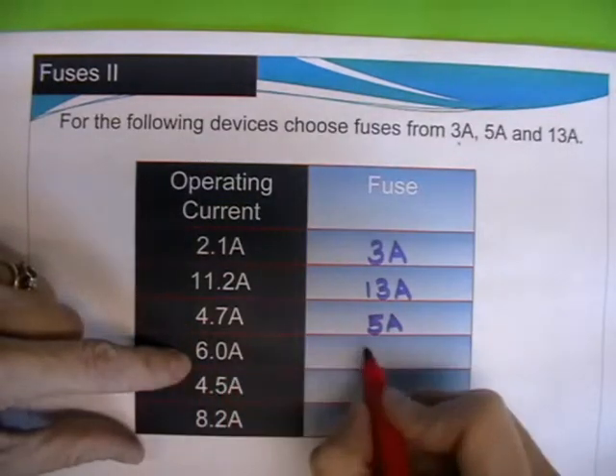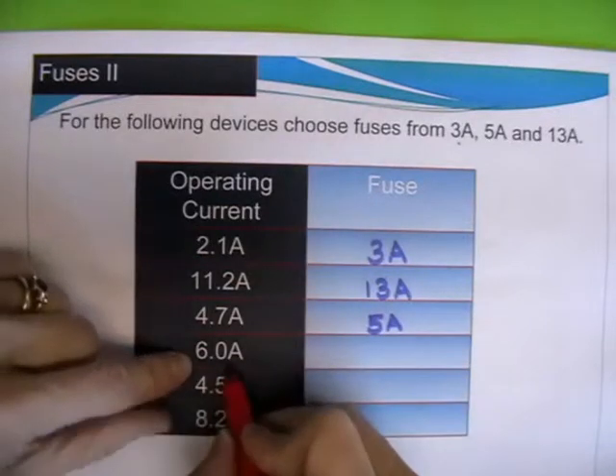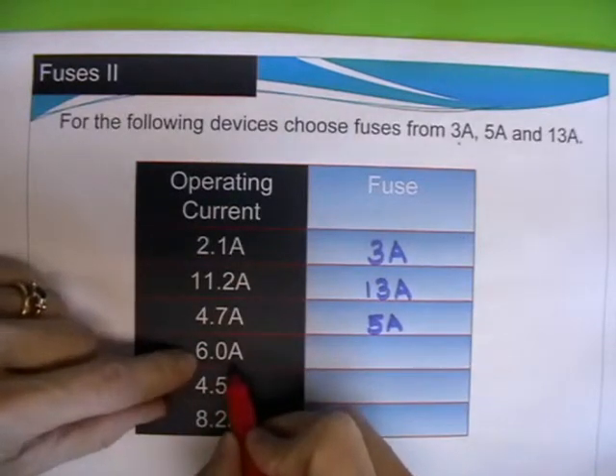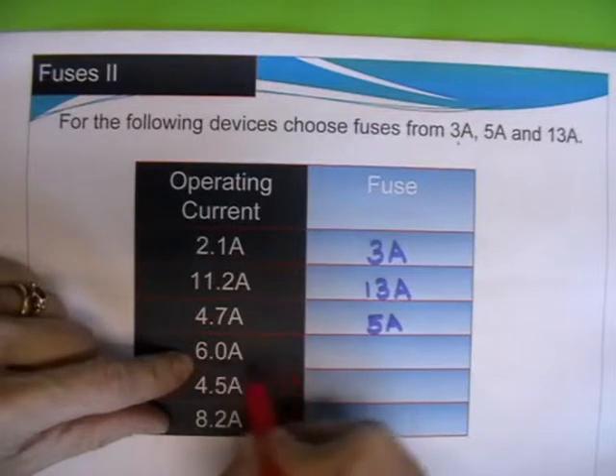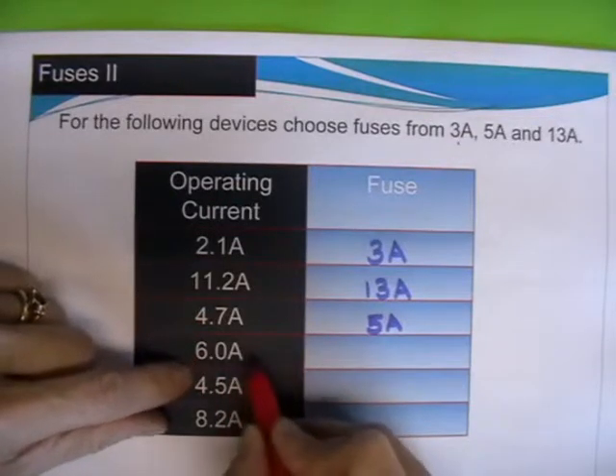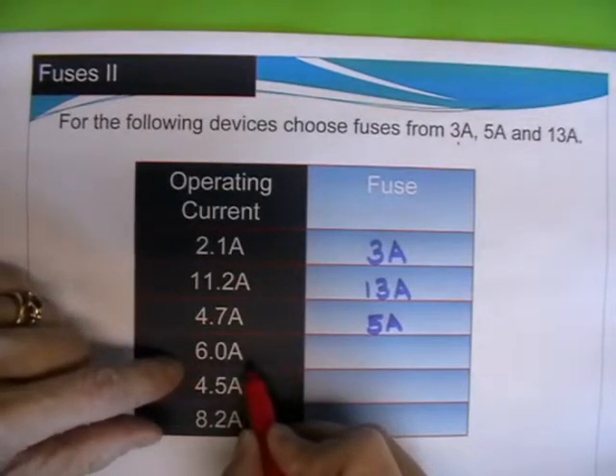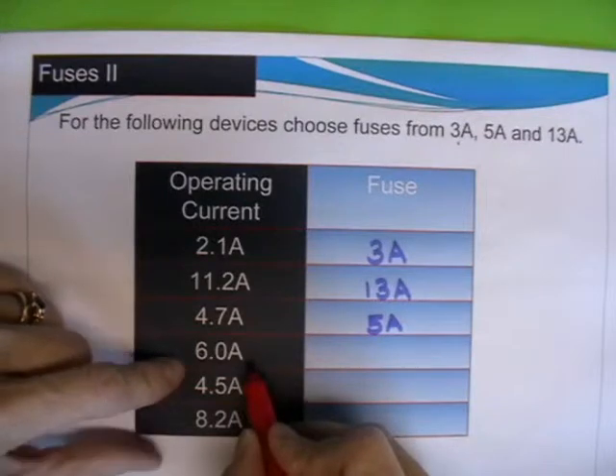6 amps, now this is a funny one because it will allow up to 13 amps to flow before it breaks, since there's no other fuse in between. So your device is fitted with a fuse suitable for it.